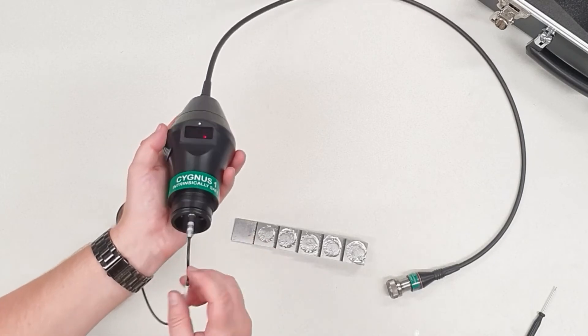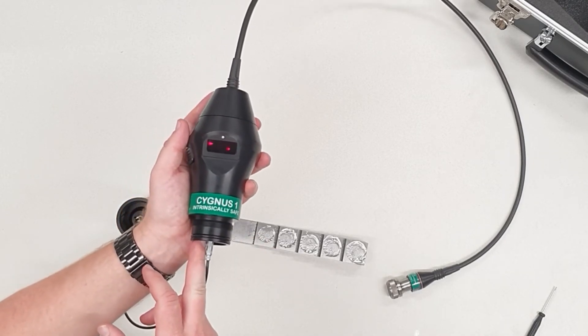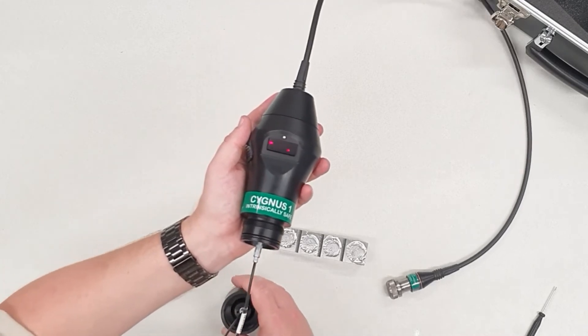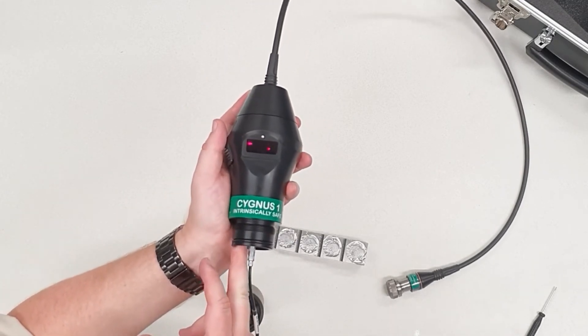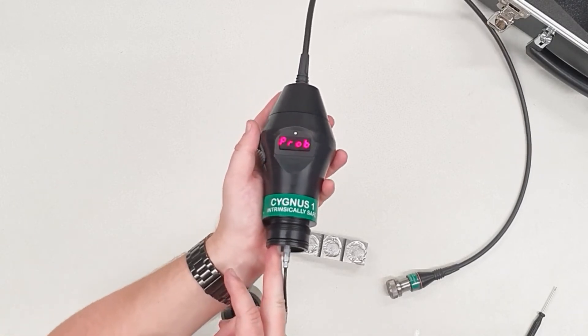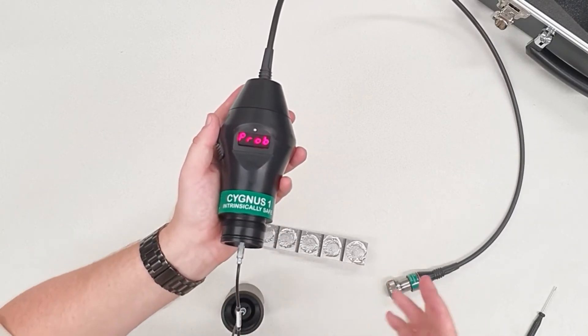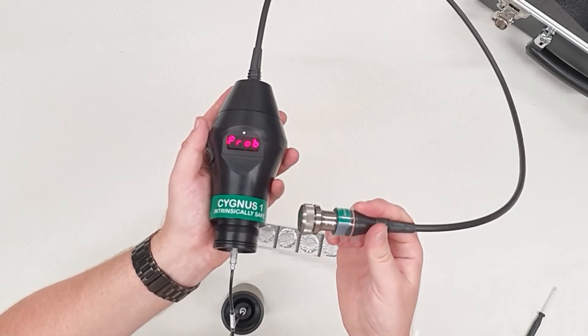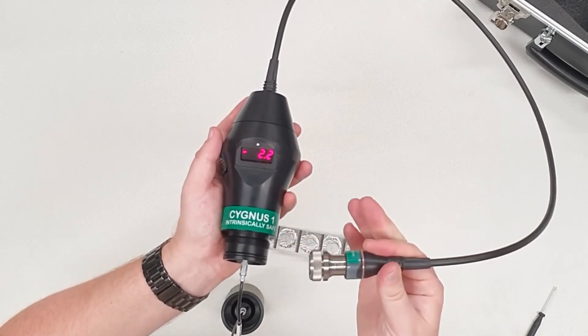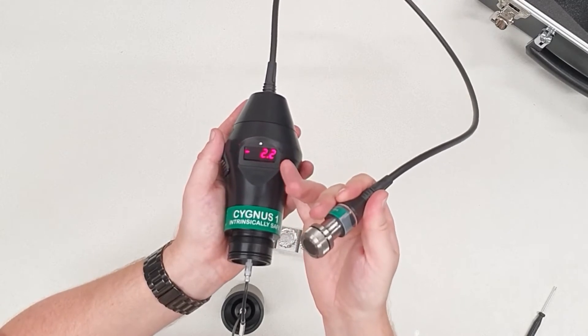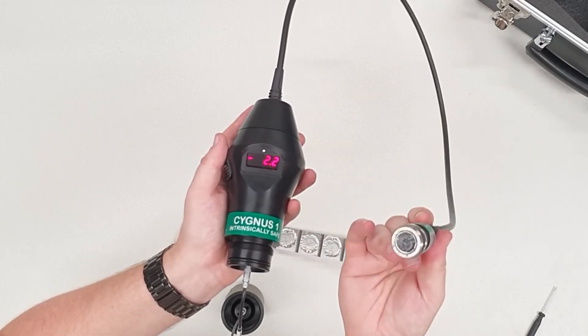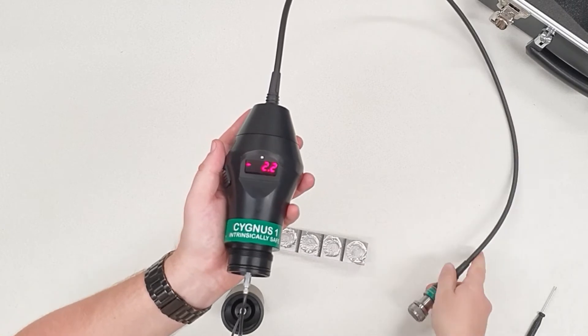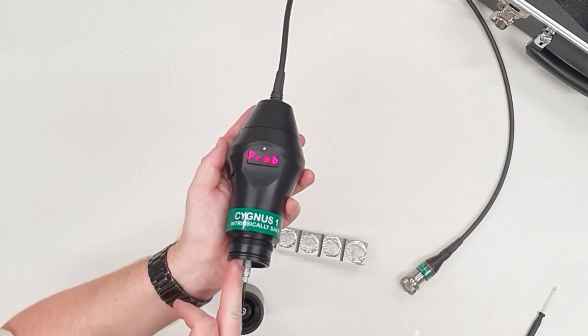There is another control underneath, a small button you can press that takes you through other settings. First setting is the probe frequency. You've been provided with S2C probes: S means single crystal, 2 means 2.25 megahertz, and C is the size of the probe, 13 millimeter.